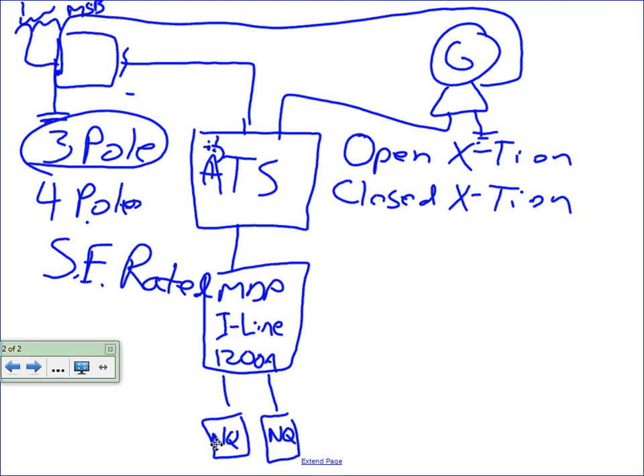Switchgear is designed to wait. You can set the breaker up to wait up to 30 cycles. So why is that important? For coordination. You can coordinate with the downstream devices, because you want that main gear to sit there and hold that fault for as long as you possibly can to allow that downstream device that's closer to the fault to take that fault out.